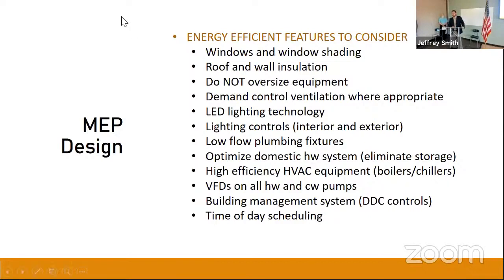It is permitted, yes. So we can drop that amount as long as you're sensing it. With the CO2 sensors, they want to keep it above or below a certain level. So the code permits you to take it down to a certain level. And then once you see a certain level, it will start to adjust and open the dampers and allow more in.